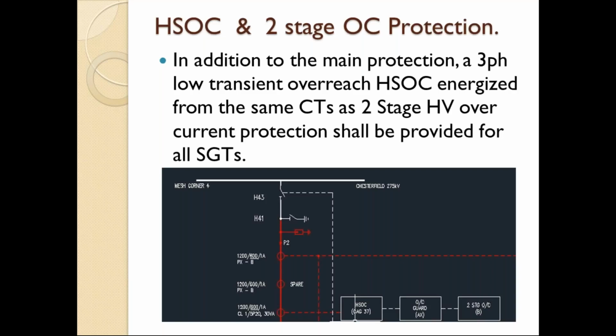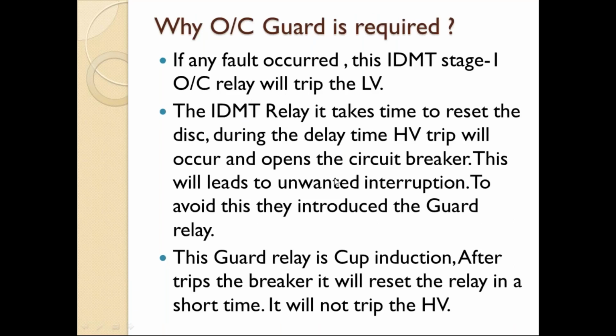So that is nothing but inverse definite minimum time, IDMT relay, and they will be using that. What is the problem in that relay is if any fault occurs, the relay will take time, and the disk will take some time to operate. So if there is any fault occurring in that LV side, due to the delay time, the HV breaker will also trip. That's the reason this IDMT relay has this type of problem.